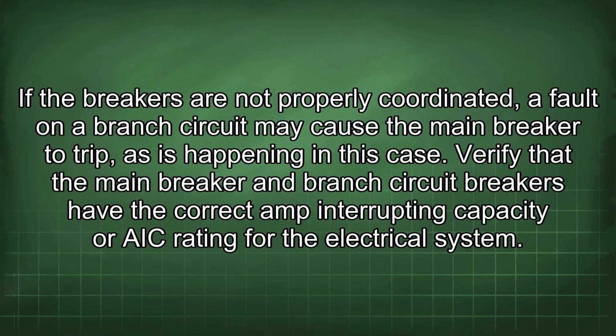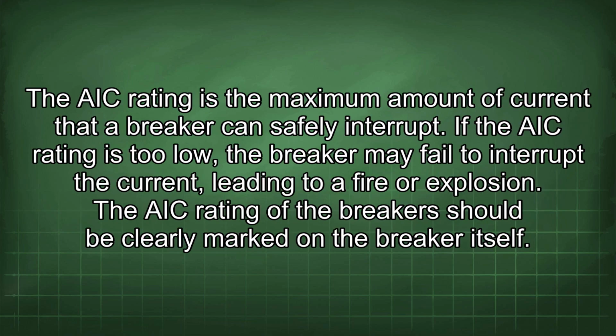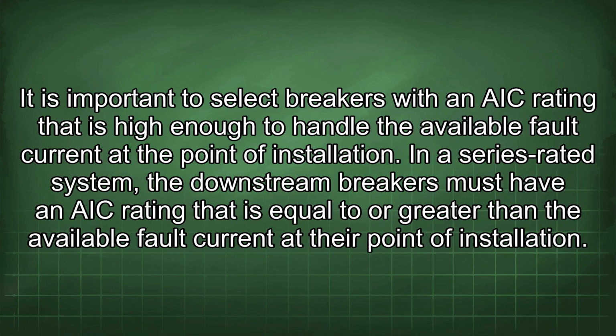Verify that the main breaker and branch circuit breakers have the correct amp interrupting capacity, or AIC, rating for the electrical system. The AIC rating is the maximum amount of current that a breaker can safely interrupt. If the AIC rating is too low, the breaker may fail to interrupt the current, leading to a fire or explosion. The AIC rating of the breaker should be clearly marked on the breaker itself. It is important to select breakers with an AIC rating that is high enough to handle the available fault current at the point of installation.